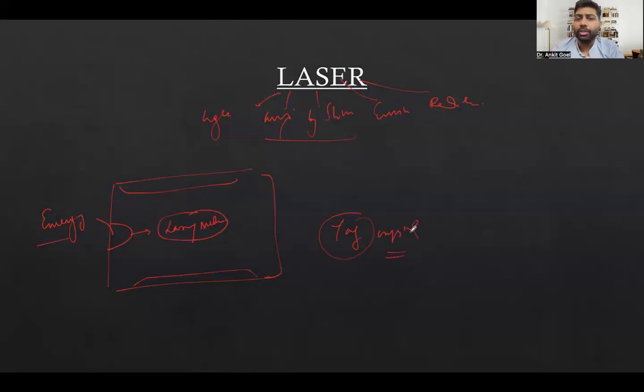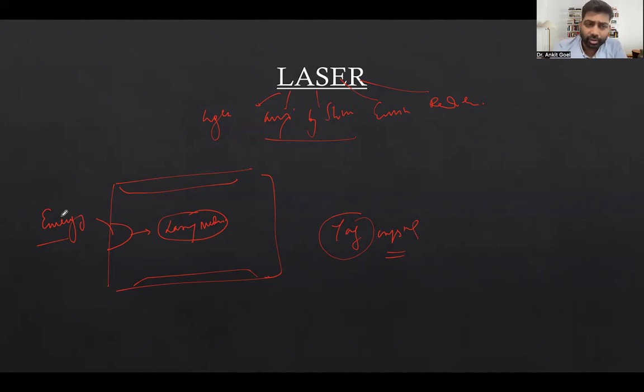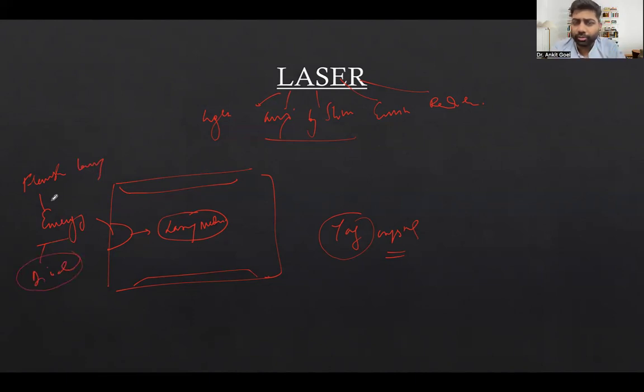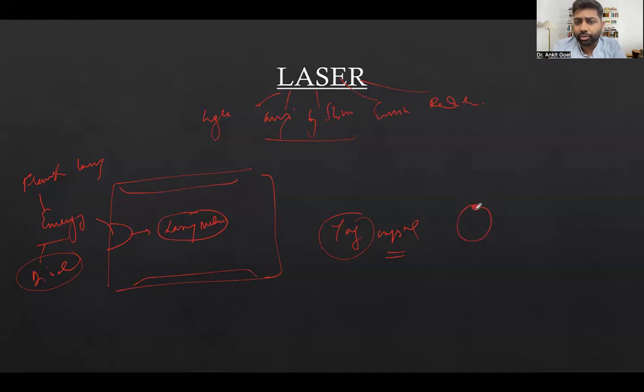YAG is the lasing medium. It has crystals which release photons. The energy source — which can be a flash lamp or a diode — releases energy to activate the lasing medium. When the lasing medium is activated, the atoms which have electrons in a stable phase receive energy, and these electrons are excited to higher orbits.